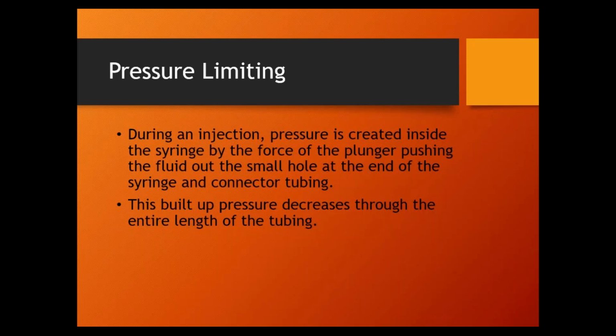The catheter, that's inside the patient. That's what determines the pressure limit. Catheters have a pressure rating. When they get the catheter out of the packaging, one of the items of information on that package is the pressure rating, or max pressure. Whatever that number is, that's what they put on it. There's no need to go any less than that. The operators will dial in the protocol, and the protocol calls for 800 psi or something like that.